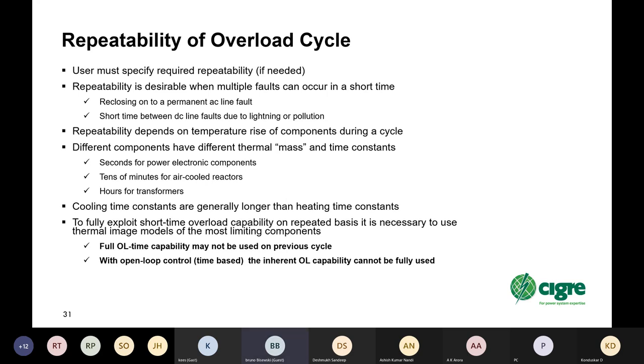So to fully exploit short time overload capability on a repeated basis, it is usually necessary to use thermal image models of the most limiting components, because the full overload capability may not be completely used up on the previous cycle. If you have a thermal image model, you can remember how much of that capability you used on the previous overload cycle and extend the current overload cycle if you need to, or go to the limit on it if it's possible. If you have an open loop control where you have a time-based wait between overload cycles, then the inherent overload capability of the equipment can't be fully used.